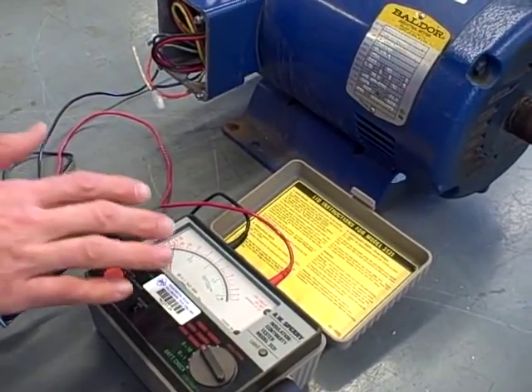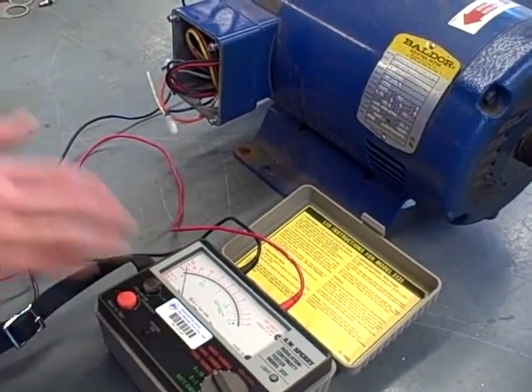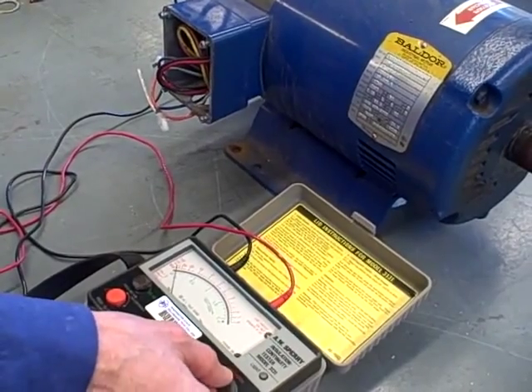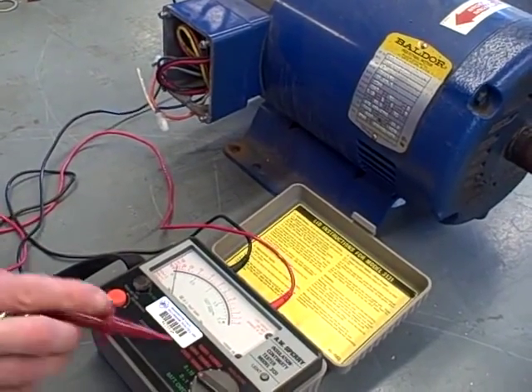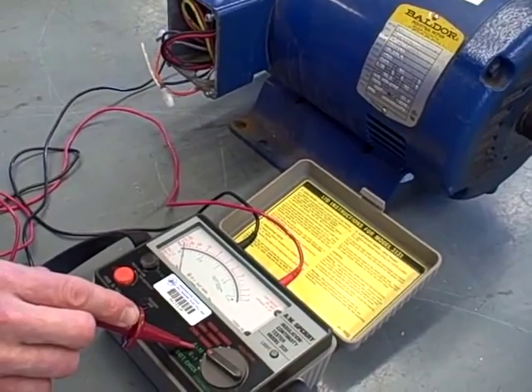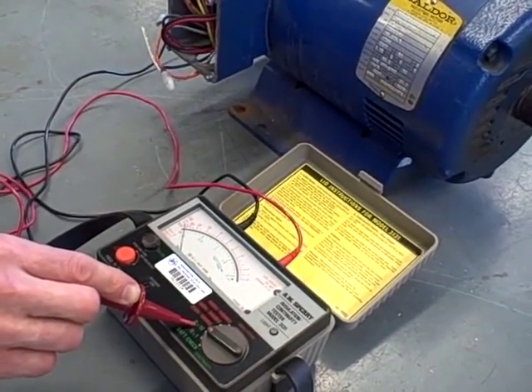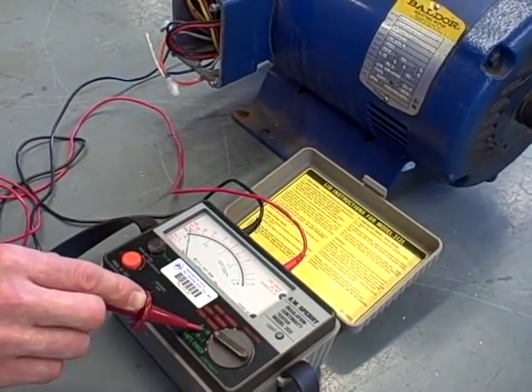Now just to prove to you that the high voltage actually matters, it makes a difference to our measurement, I'm going to switch this to the low voltage range. In the green mode, this right here is acting as a typical ohm meter. And as a typical ohm meter, it uses a very low voltage to test for resistance.